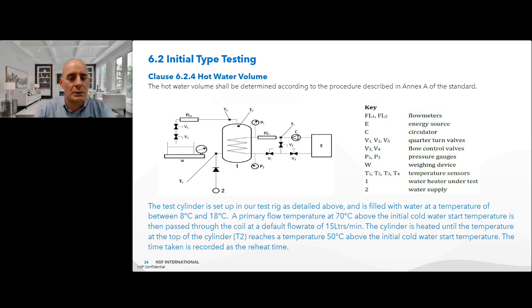You can see the diagram of the setup then. E is your bulk heat store. You've then got a circulator, a flow meter in the primary loop, and control valves to accurately adjust the flow rate. You've got pressure gauges as close as possible to the coil connections, then the draw off pipe, again with another flow meter and control valves to accurately control the draw off rate. And that then goes into a container on a weigh platform.